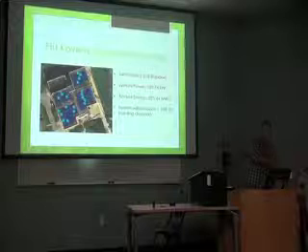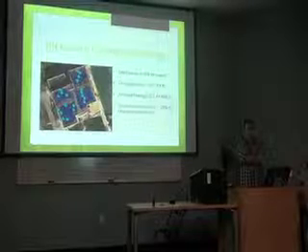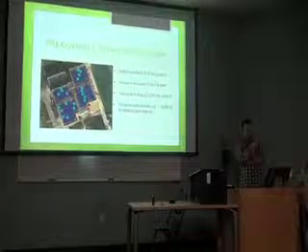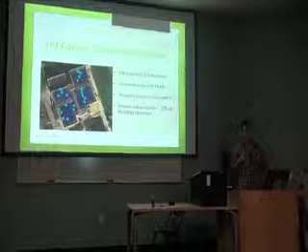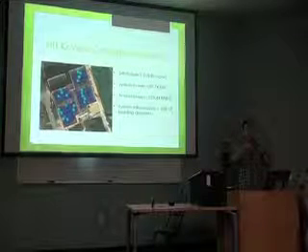Basically, a customer said to me, okay, cool, I have my grid-tied solar system, no batteries, sweet. So the power goes out, I still have power, right? The answer is no. The reason is, when the power goes out, there are workers working on the grid, working on the lines, and you don't want to be sending power back to the grid. You don't want to be backfeeding power. So the inverters have to be equipped with a mechanism that shuts them down when they don't read power coming in from the grid.